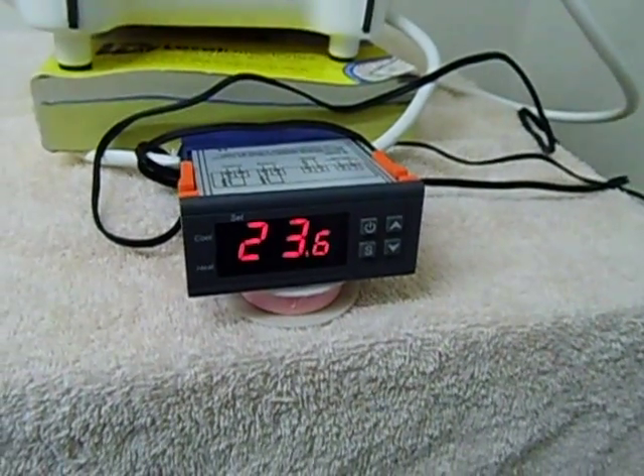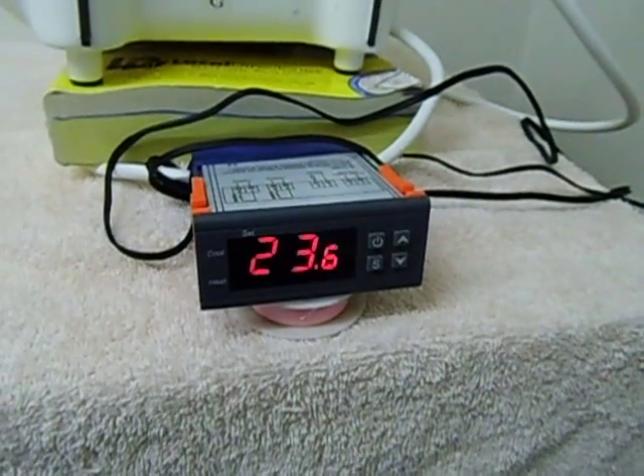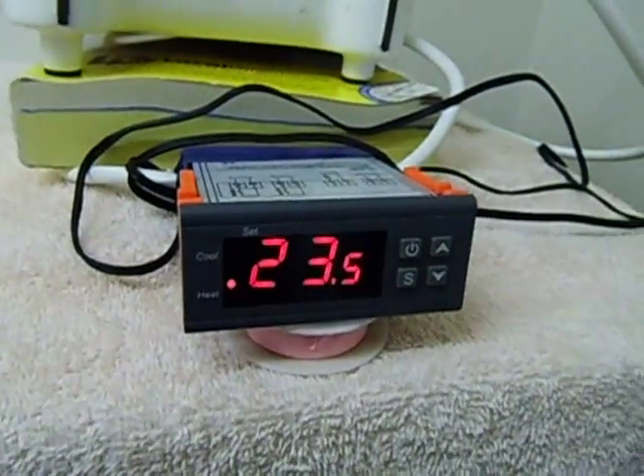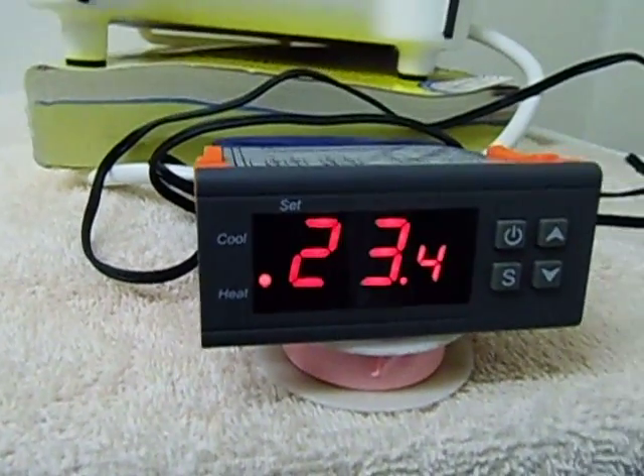When it gets to about 23.5 degrees, the fan will automatically kick in, except for one degree difference. So this room will maintain its heat between 23.5 and about 25 degrees, which is only that one and a half degree difference. There it just kicked in — you can probably hear the fan blowing. The light is on, showing it's heating.